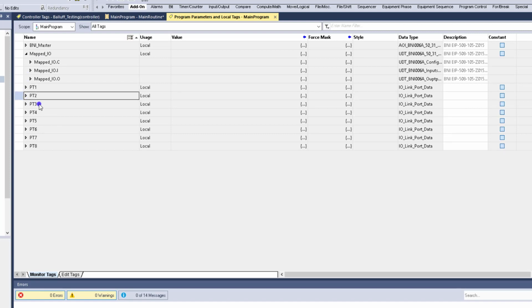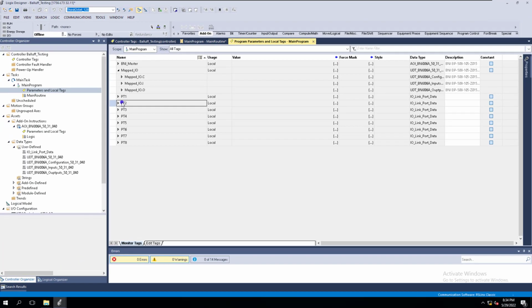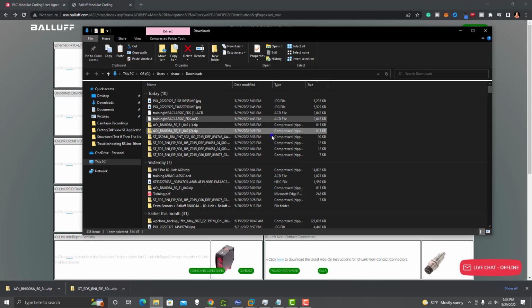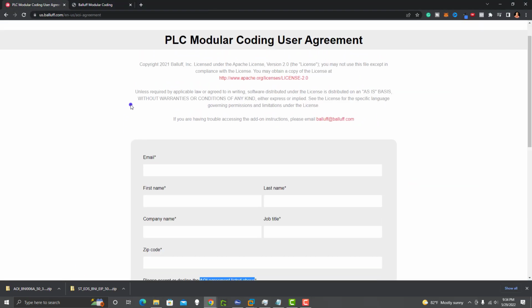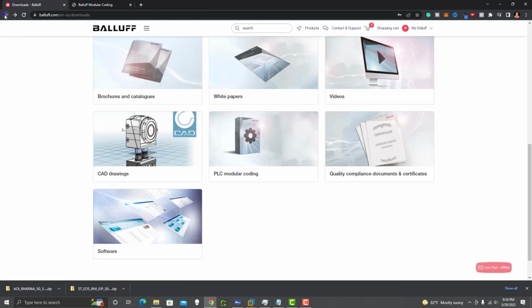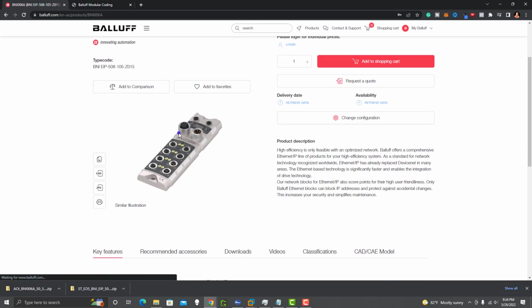Another key component to this is that if you make a change to your PLC program and you download it and you're not getting a good response, you need to cycle the power to the actual IO device. If we're talking about the device that we were showing right here, let's go back to our devices.